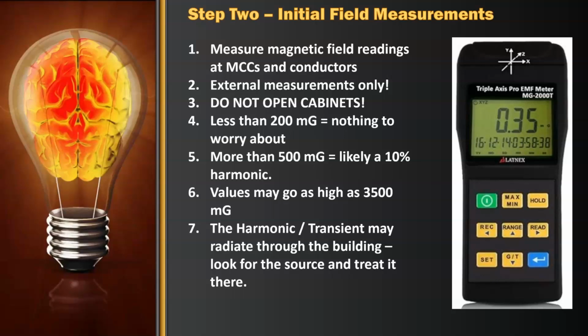Yep. If I went to the primary meter, I'd find out, hey, is this primary meter being exposed to harmonic? And okay, it is. So now I'm going to go look at the MCCs in the building. Which MCC is causing this? When I'm at the MCC, I'm going to take this meter and just run it down the front of the panel, and look at the circuit and look at the reading. These meters take about a second or two to respond. So you want to count 1001, 1002, 1003, and you'll see the number pop up if there is a problem. And from that, I'll want to see where the equipment is that's causing the issue.